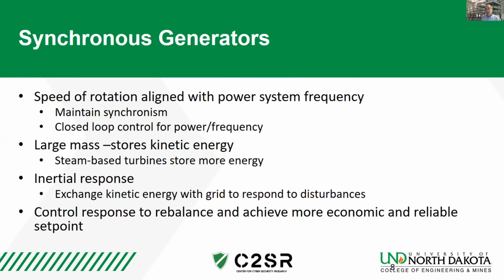As the transition has gone from steam-based plants, whether coal-fired or nuclear, to gas turbines or renewable energy with inverters, we're losing some of the spinning mass associated with the stages of a steam turbine. Some utilities have talked about taking decommissioned steam plants and converting them into reactive power sources, or synchronous condensers. But if they cut away all that mass, they have a lot less inertia to provide, so some are adding flywheels to those.